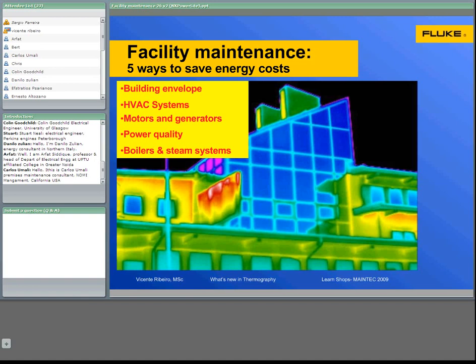And as I said, electrical connections. I gave the example of the problem we had on the building where the European Commission is working, and that can be explained by a simple case like this. You can see here cables, and one of the cables has a temperature of 75 degrees. Well, 75 degrees is above the limit of the insulation of the cable. PVC cables have a limit.